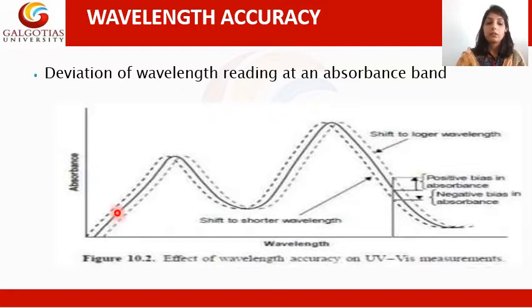Then the wavelength accuracy. Here is a diagram representing the wavelength scale and the absorbance. This is the graph you need to obtain. But if you are getting absorbance at a particular wavelength that is either higher or lower, suppose at a particular wavelength like 240 the absorbance value should be 0.6, but you are getting 0.8 or 0.4, then in both cases we observe certain shifts in the wavelength, which is due to the instrument not being properly calibrated. Either we observe a shift towards the positive side, that is towards longer wavelength, or a shift towards the negative side, that is towards shorter wavelength. By this we can observe whether our instrument is calibrated or not.